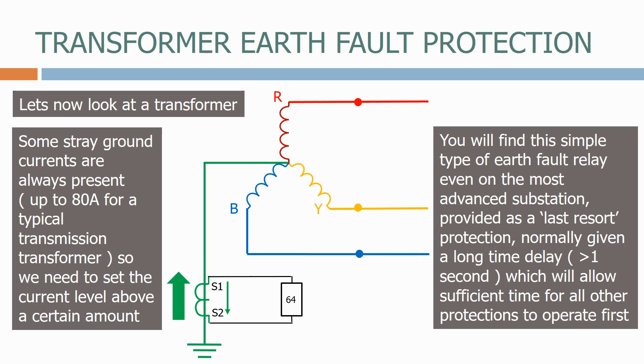You will find this simple type of earth fault relay even on the most advanced substation, provided as a last resort protection. Normally given a long time delay, greater than 1 second, which will allow sufficient time for all other protections to operate first.